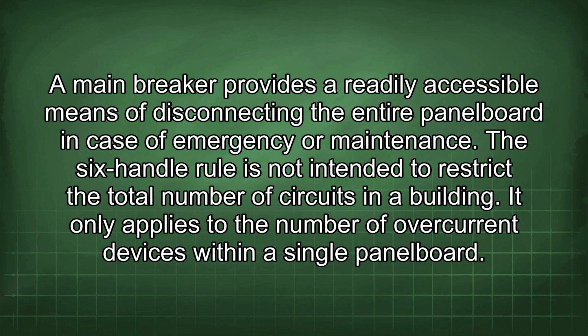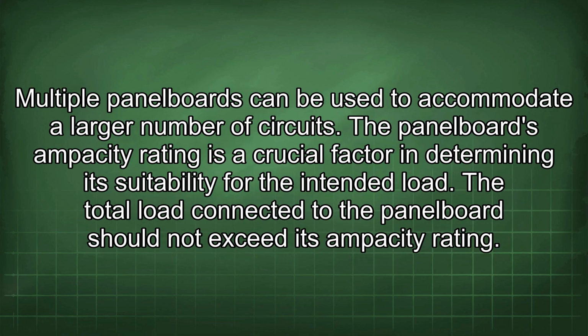The 6-handle rule is not intended to restrict the total number of circuits in a building. It only applies to the number of overcurrent devices within a single panel board. Multiple panel boards can be used to accommodate a larger number of circuits. The panel board's ampacity rating is a crucial factor in determining its suitability for the intended load.